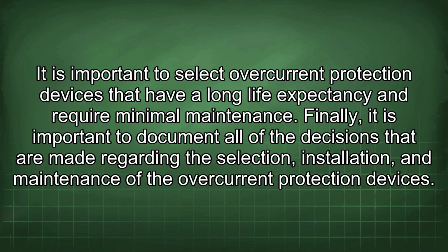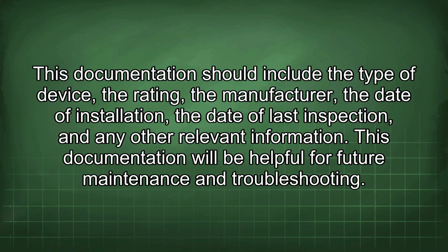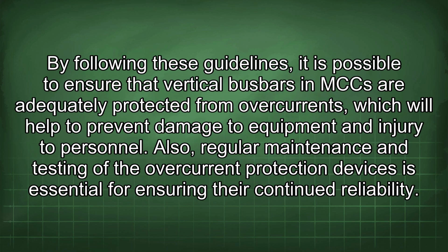Finally, it is important to document all of the decisions that are made regarding the selection, installation, and maintenance of the overcurrent protection devices. This documentation should include the type of device, the rating, the manufacturer, the date of installation, the date of last inspection, and any other relevant information. This documentation will be helpful for future maintenance and troubleshooting. By following these guidelines, it is possible to ensure that vertical busbars in MCC are adequately protected from overcurrents, which will help to prevent damage to equipment and injury to personnel.